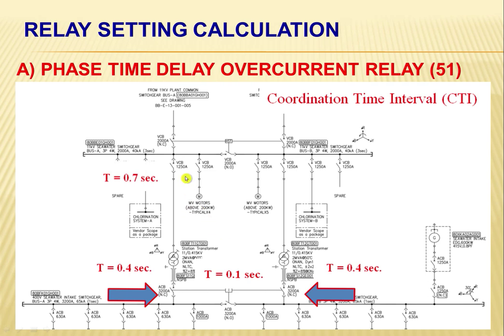This is for the primary side of the transformer. Okay, and on the incomer side of the 11 kV switchgear, we have also the time delay of 1.0 seconds. So here, the time interval, if you notice, we have 0.1, 0.4, 0.7, and 1 second. The time interval here is 0.3 seconds. Okay, so in our point of discussion, our time delay is 0.4 seconds. So from seeing this, we have performed a proper coordination in terms of our time delay.